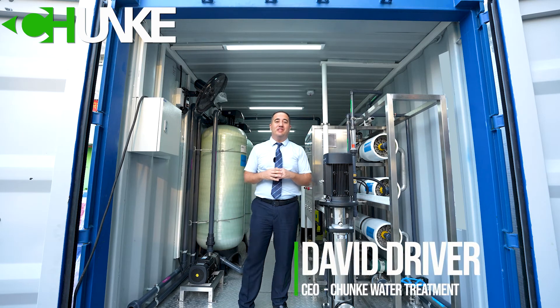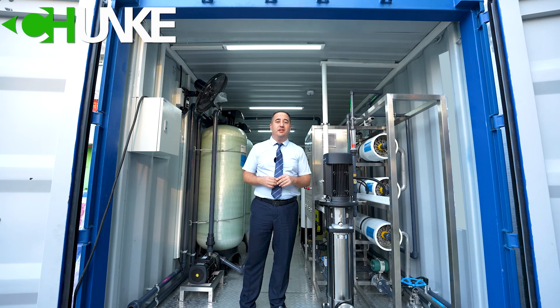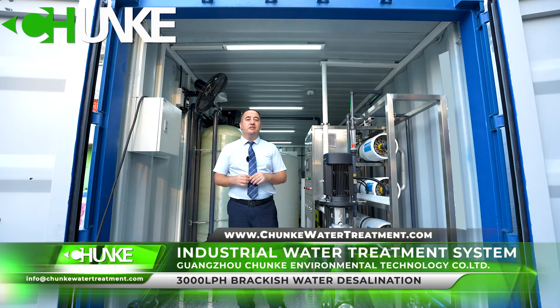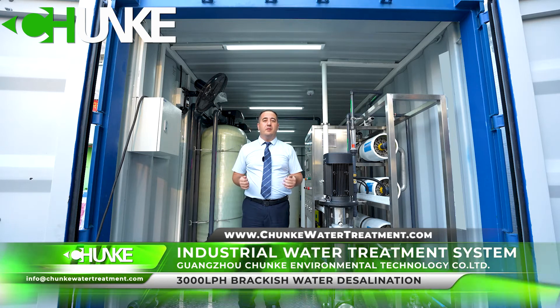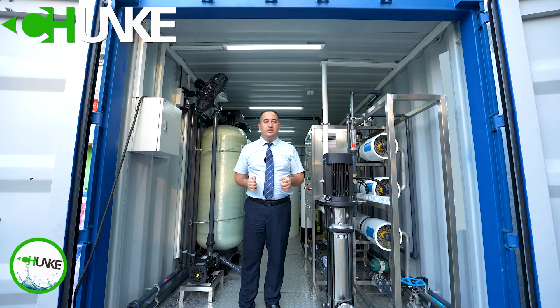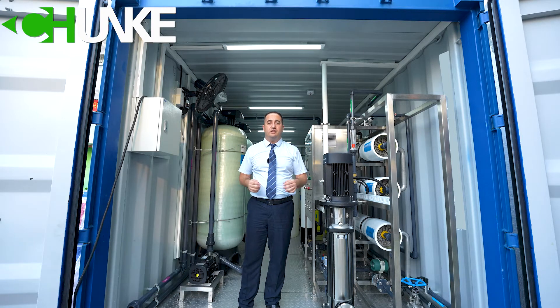Hi, this is David from Chunke Water Treatment. Today we have finished another project: a containerized water treatment system. This system is 3000 liters per hour water capacity. Water source is underground water, deep well water. Water TDS is around 2300 ppm. So this system is a brackish water desalination system.